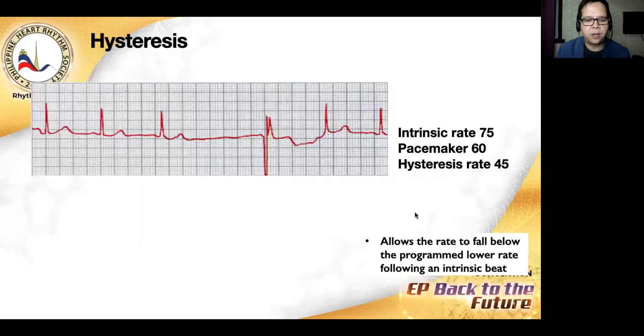Now, sometimes pacemakers are programmed with a so-called hysteresis rate. So this feature basically allows the patient's own intrinsic rate to come in before the device delivers a pacing spike. So for example, in this tracing from a patient with a VVI pacemaker that is programmed to a lower rate of 60 beats per minute, and the hysteresis rate is 40 or 45 beats per minute. The first 3 beats are intrinsic sinus beats at around 70 beats per minute. And then the patient goes into a short pause.